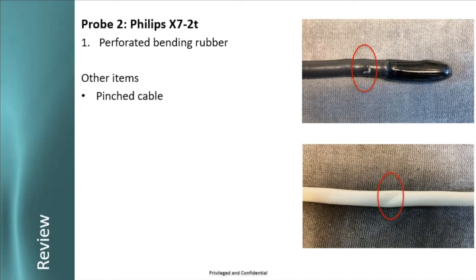What we recommend - and this is one component of the SafeTEE program, there are three other components, I'd love to sit down with you guys and talk about some best practices - TE probes should be transported in a large bin. You should never coil them smaller than a 1 foot diameter. Those bins should include a contaminated bin and a clean bin, so it's transported in the contaminated one, and once cleaned and disinfected, it goes into a clean bin for storage. They should never be stored in those bins long-term, because these insertion tubes will create a memory, and if kept coiled over time they'll want to stay coiled. They should be hung in a tube in an approved cabinet, ideally one with positive air pressure and a HEPA filter, which keeps dust and debris out of the cabinet and off the probes.